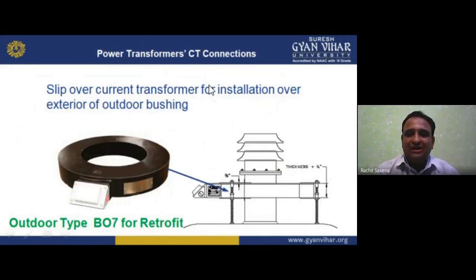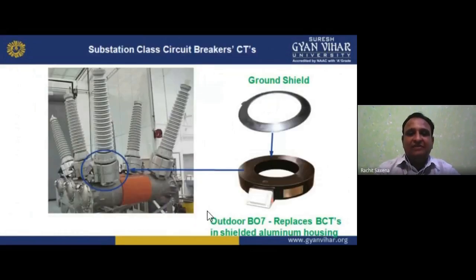So a slip over current transformer is for installation over the exterior of the outdoor bushing. We have bushings on the power transformer, so we place the CT there, for the current measurement, low voltage and high voltage. So outdoor type BO7 for retrofit we have, similar to that. Then we have a ground shield like this for the circuit breaker CT, substation class circuit breaker, and we have the ring structure of window CT, which we place here for the current measurement. That is the ground shield. And outdoor BO7 replaces the BCT in a shield aluminum housing. So we are using the ground shield instead of others.